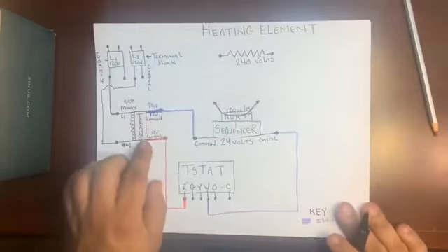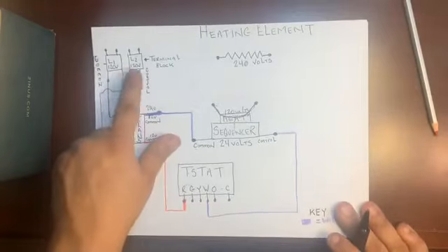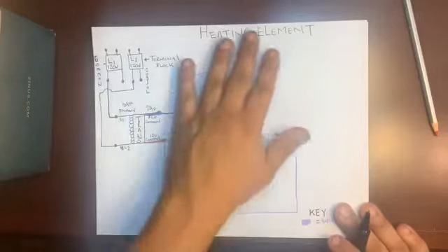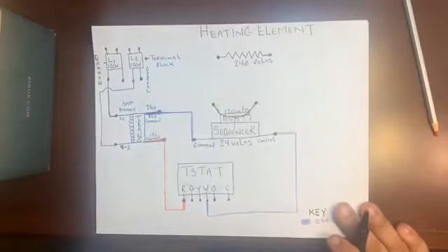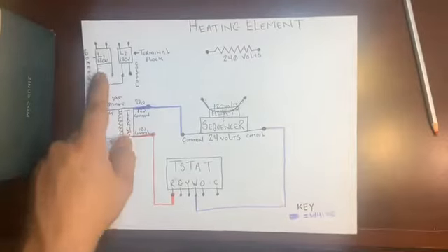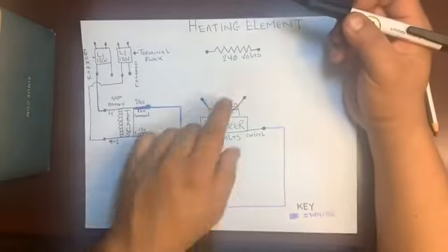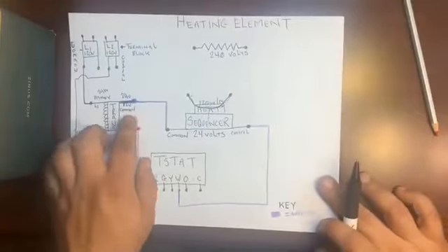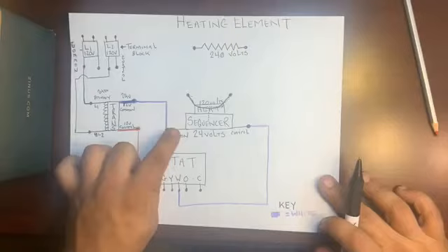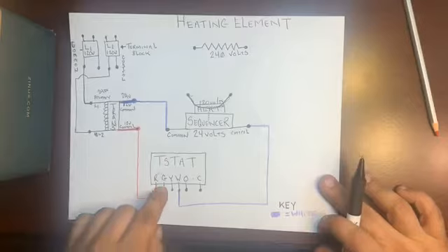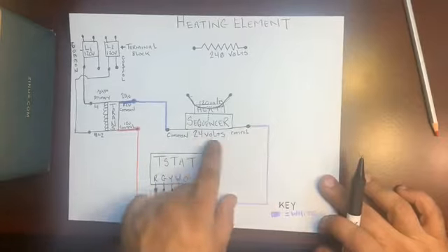Just as the secondary side of the transformer has common and control, L1 and L2 also have a common and control side. Let's see how these two tie in. Once you tie in the common and control for the high voltage, then you understand the whole diagram, how the low voltage works with the high voltage. Okay, so if we designated a common on L1, let's bring power over. We need 240 volts to turn on this heating element. So what does common do? If we look at common here, common provides a constant 12 volts, if you will, to this common leg of the heat sequencer, which lets us manipulate the other 12 volts through the thermostat to give us 24 volts.